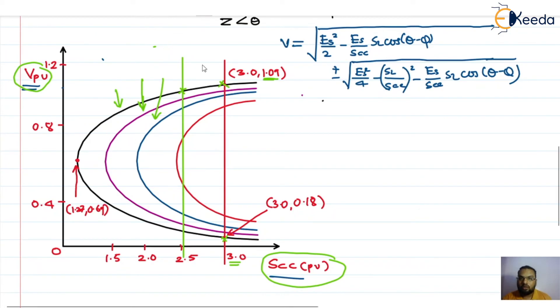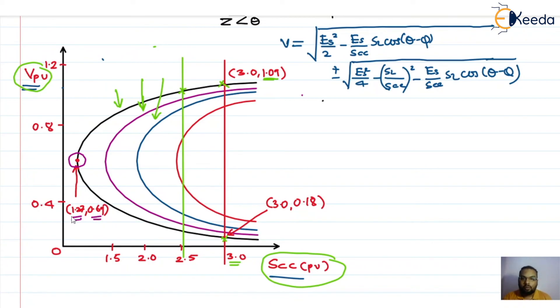One important point: if we operate at a short circuit capacity corresponding to 1.27 per unit, the upper and lower voltage values converge to the same value of 0.69 per unit — this is the critical value. We should not operate at this critical value because a slight disturbance will cause the system to become unstable. The conclusion is: the more the short circuit capacity, the better the voltage stability.